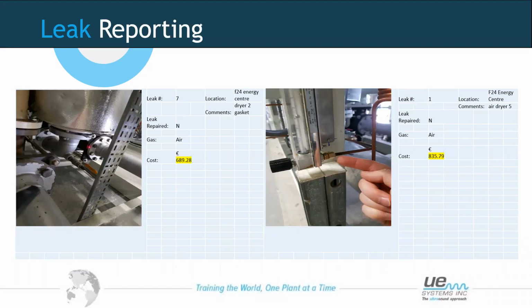Android and iPhone devices. So I have a quick question coming in, asking whether chillers and HVAC refrigerant gas leaks can be captured. So again, on chillers, we have a pressurized system. If we have a leak, we're going to have turbulence, and the answer to that is yes. I've used it on large HVAC systems. I've even been into local cooperative stores and checked refrigeration systems there and identified leaks with ultrasound too. So yes, it is possible. So that's the coverage of leak reporting for now.